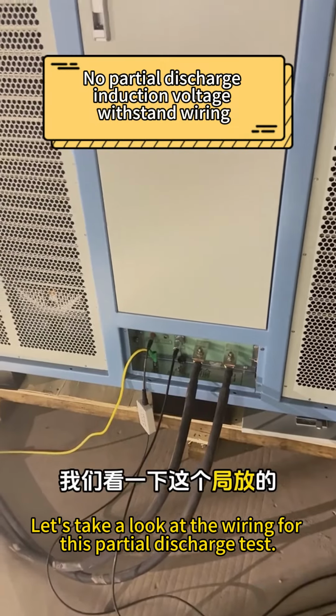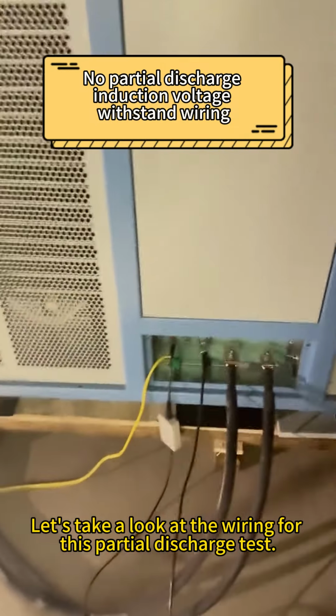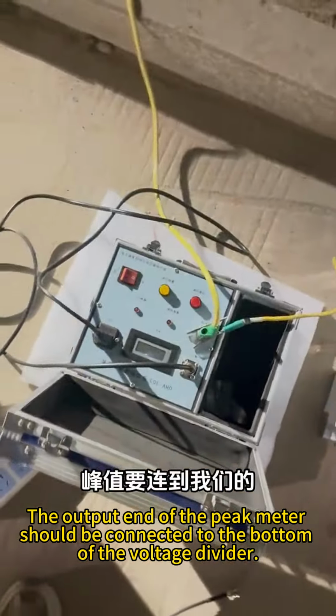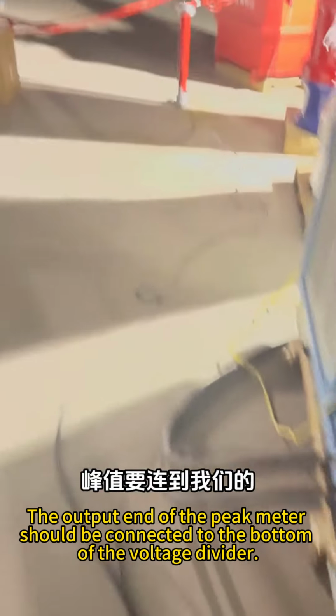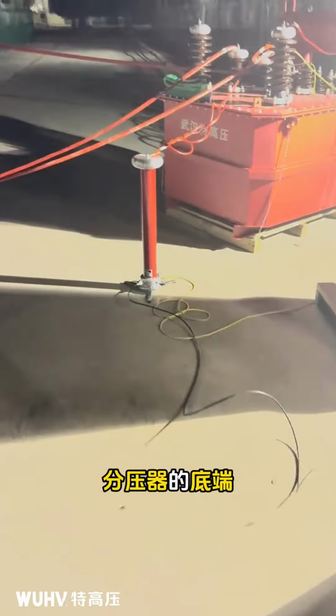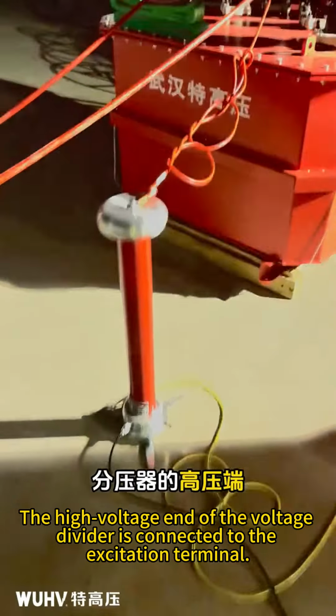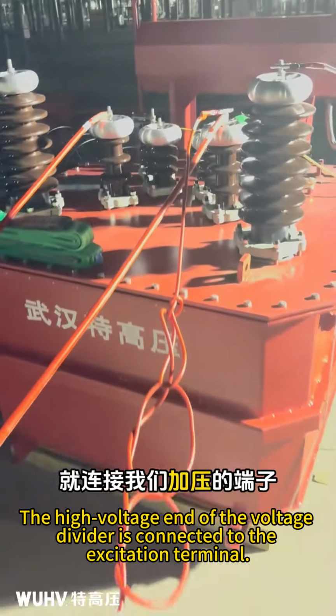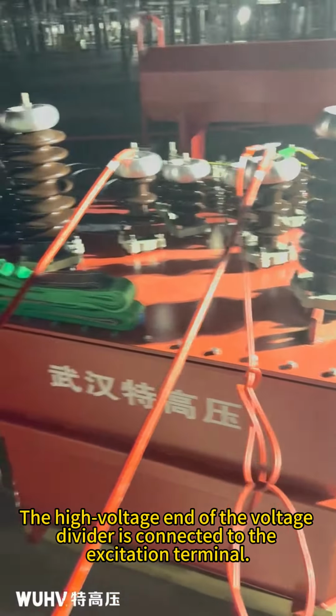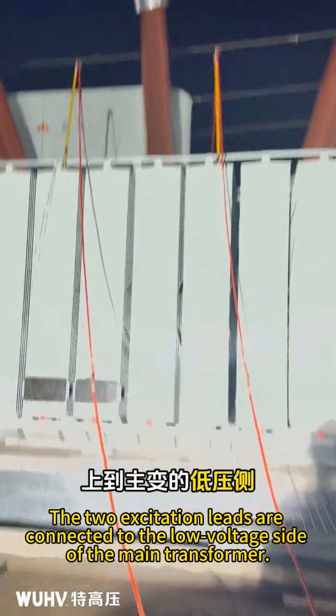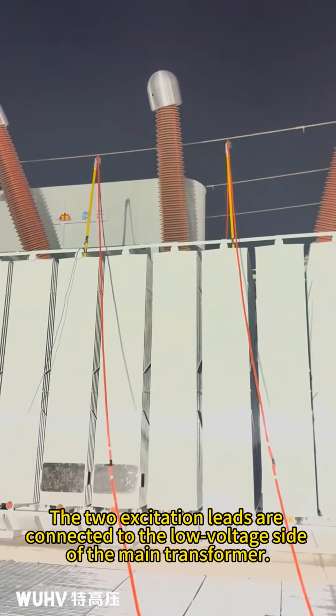Let's take a look at the wiring for this partial discharge test. The output end of the peak meter should be connected to the bottom of the voltage divider. The high voltage end of the voltage divider is connected to the excitation terminal. The two excitation leads are connected to the low voltage side of the main transformer.